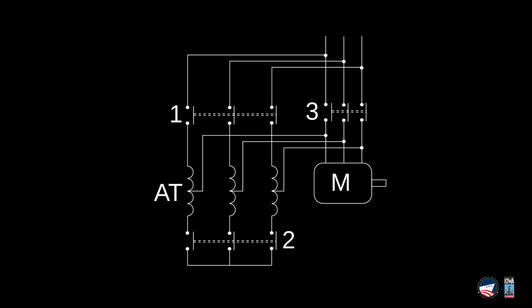In our case, we have an auto transformer starter. It's a motor starter that allows you to start the motor at a lower voltage, at a lower amperage, and reduce the startup load, that inrush current, until it gets up to speed, and then it flips over to full voltage, and off you go.